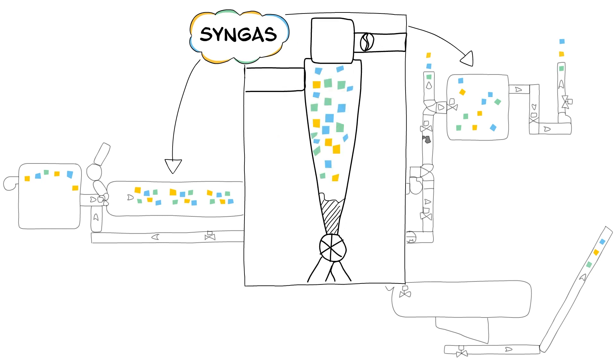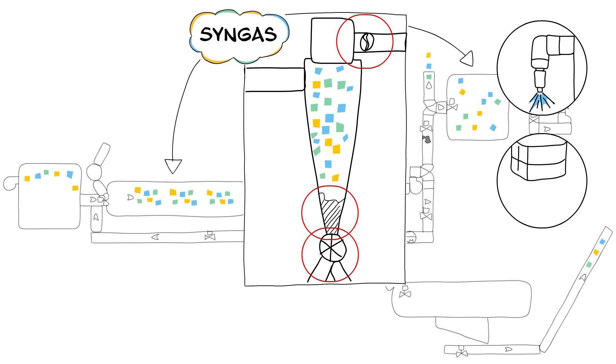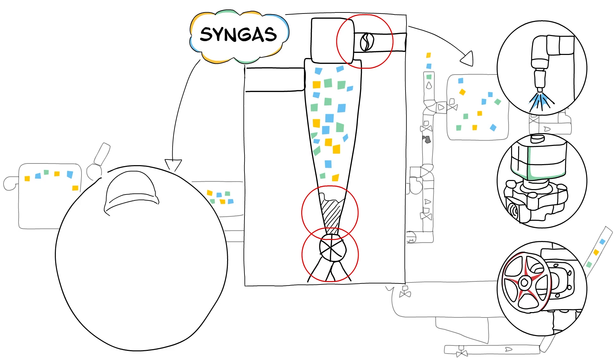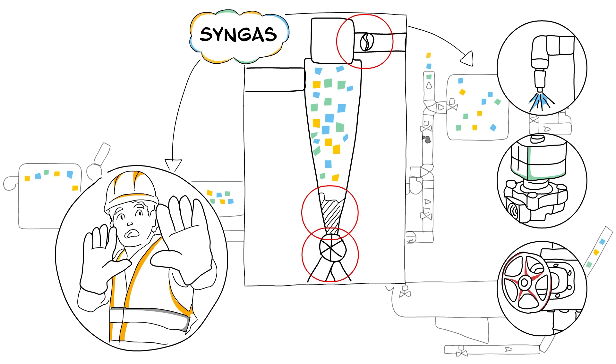Dryer component failures such as plug cyclone, in-feed airlock jam, or faulty control dampers. Faulty fire protection equipment such as plugged or missing deluge nozzles, or faulty solenoid valves on extinguishing valves. Or distracted operations where another part of the plant is having issues, causing the drying equipment to be shut down too fast.